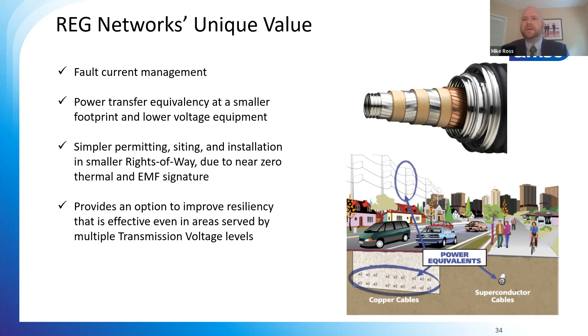So the key application in urban areas and what we call our REG applications of superconductor cables are mainly focused on interconnecting existing substations together at the distribution side. So distribution voltage levels, 13.8 kV, 11 kV, 33 kV, and so on, so that we can move power from substation to substation independent of the transmission network and the transformers associated with that. And what that means is that if we can loop substations together in a ring, like we see here at the distribution side, we can move power from substation to substation, even if there's a problem occurring on the transmission system or during the loss of transformers and things like that.